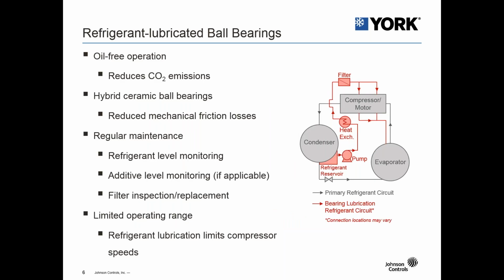So if we move on to refrigerant lubricated ball bearings, this is a relatively new type of offering in the marketplace, and it is oil-free. So in terms of CO2 reduction, there is a little bit of CO2 emissions reduction just by not having oil in the system. However, when you see the great opportunity for CO2 emissions, it's going to be in the chiller efficiency overall. These are typically hybrid ceramic ball bearings, and they have reduced mechanical friction losses, so there is some increased efficiency just from a total chiller system operation standpoint. However, there is still regular maintenance.